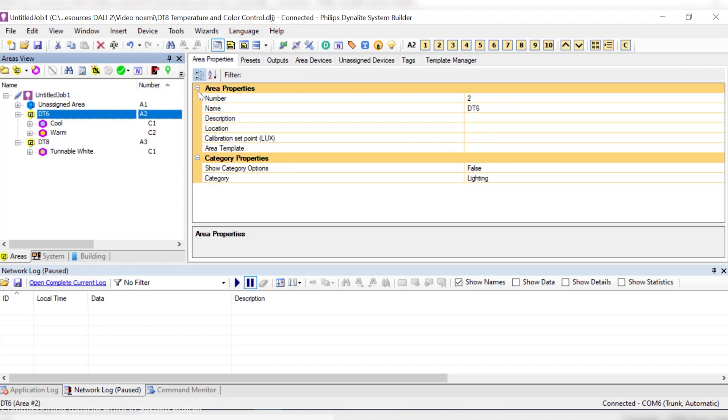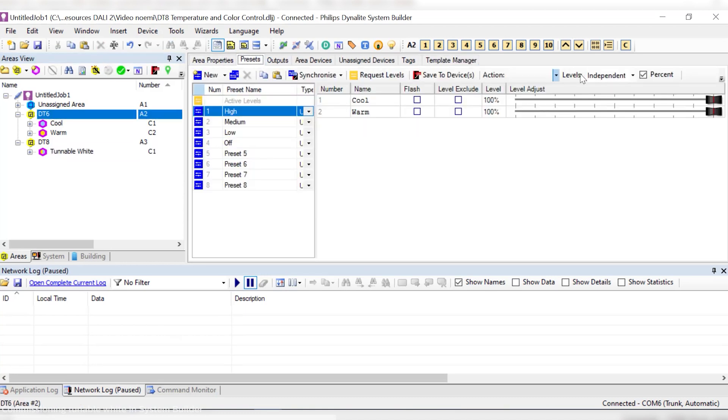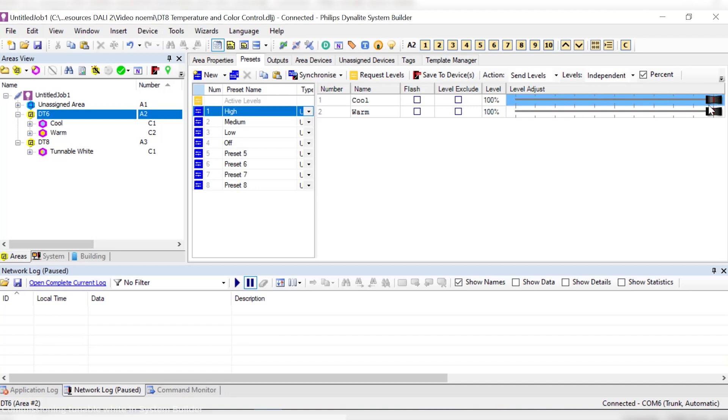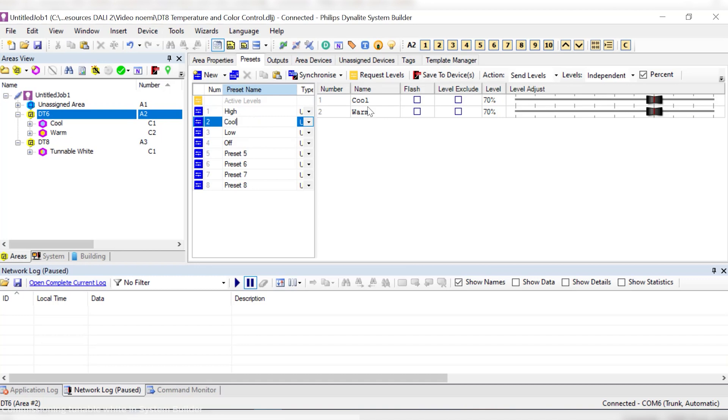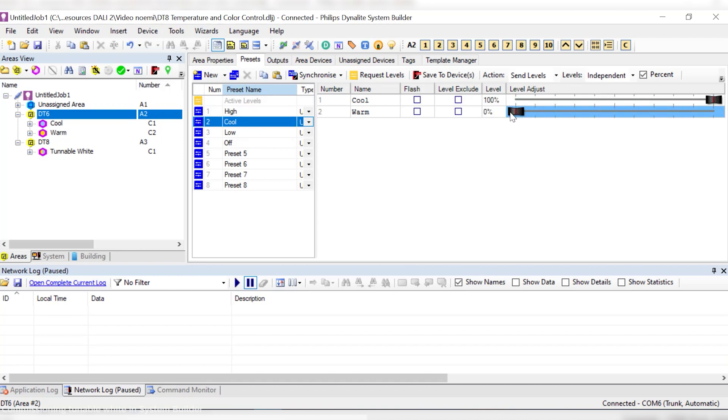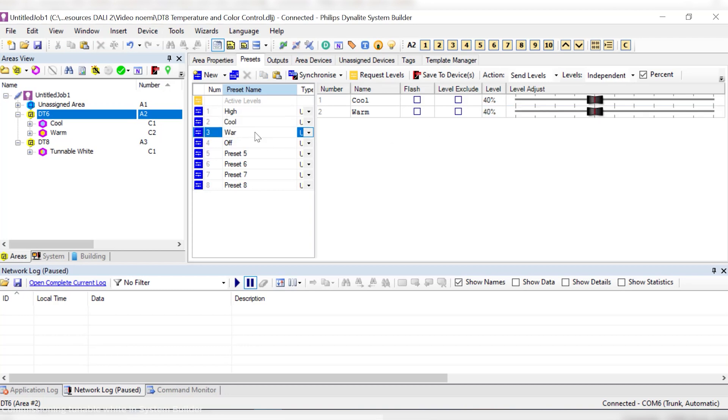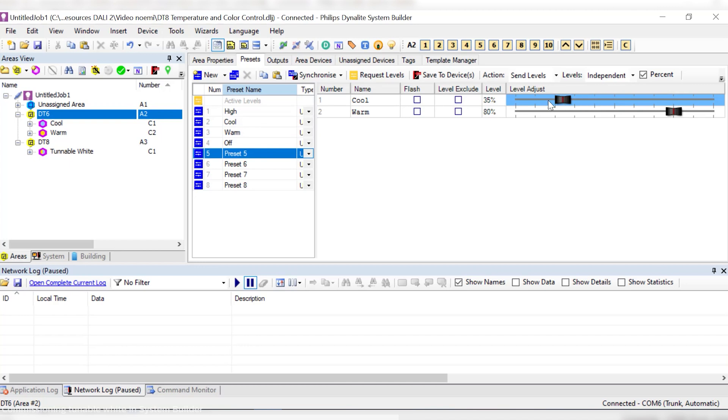Back in System Builder, we see that for our DT6 area, we will need to adjust independently the cool and the warm white channels to have the desired outcome for our scenes or presets. Creating a purely cool scene is easy as we just need to switch off the warm white channel. Same happens when creating a purely warm scene, but in this case, we will switch off the cool channel. However, if we want any other combination, we will realize that it is not intuitive at all, as there's a dependency between the channels.